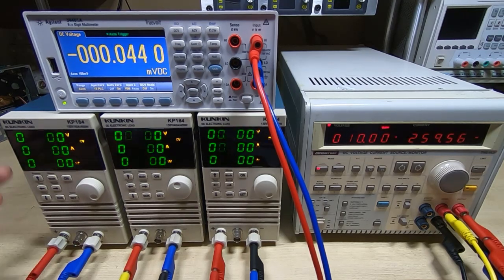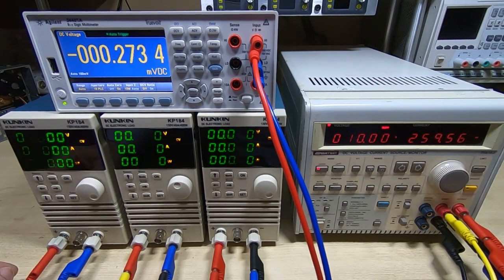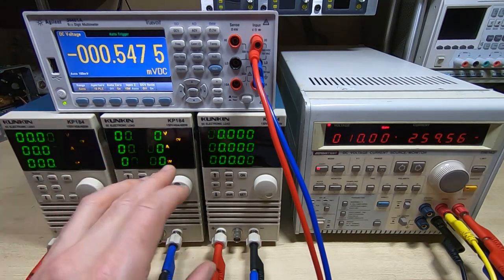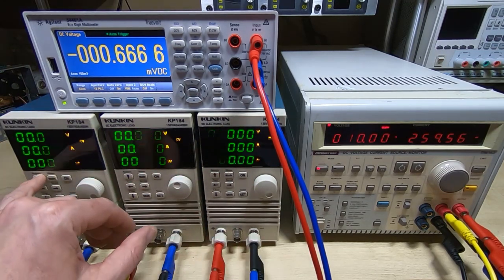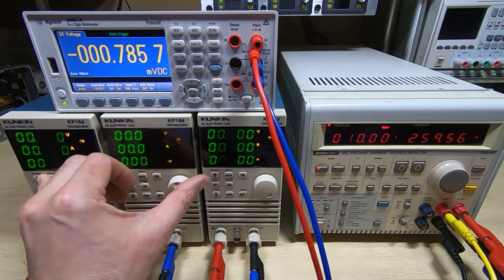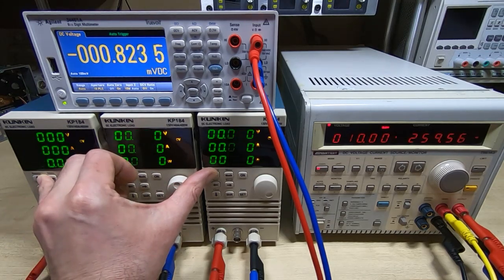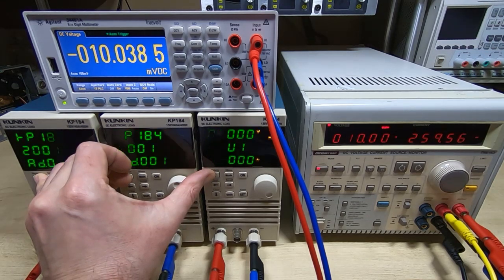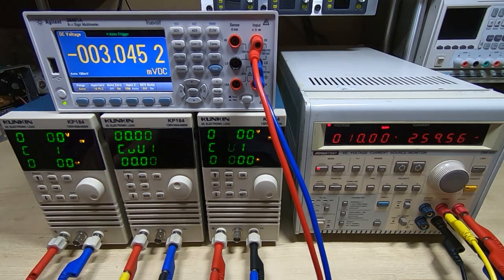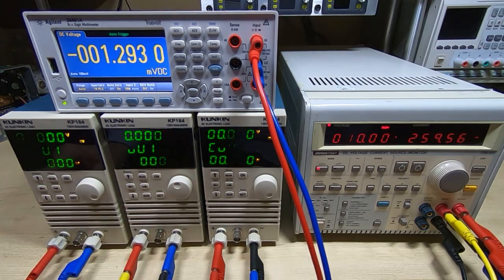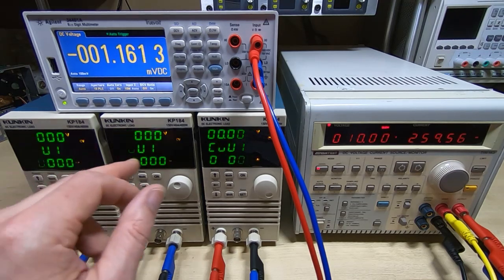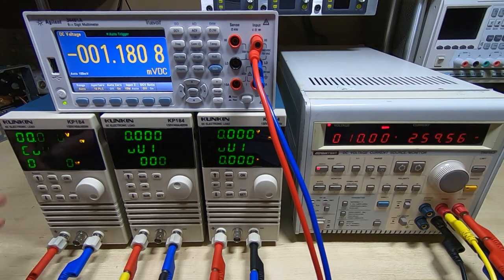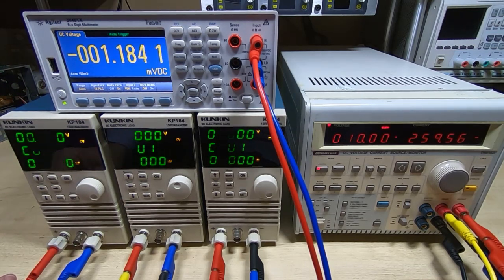I'll do all three at once. You can just do this by turning the switch off at the back but I want to do all three. The easiest way for me is to just turn the bench feed off to these and then hold all three keys in and turn it back on. I'm not a piano player so it's not particularly easy to get all three keys in at once, but I'll give it a go. As we can see we've now got the CUV1 message in the center line of each of the three loads. So it's now waiting for the first calibration point which is specified at being 10 volts.